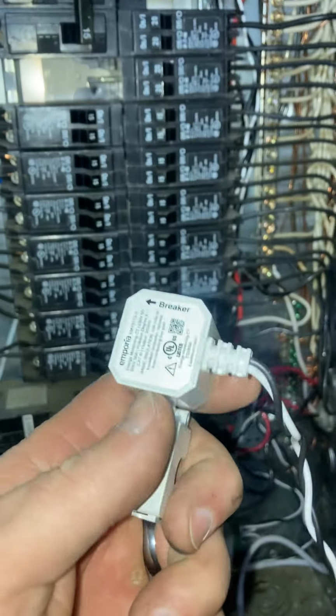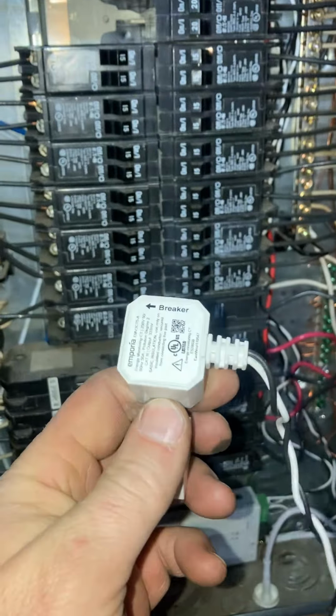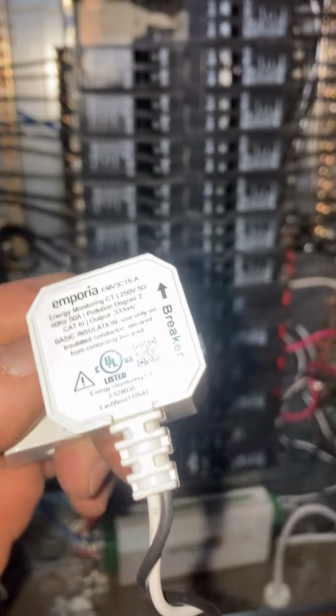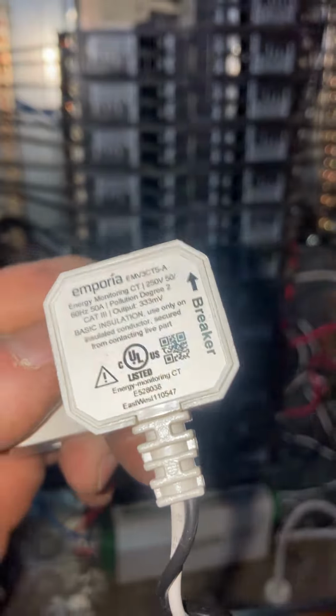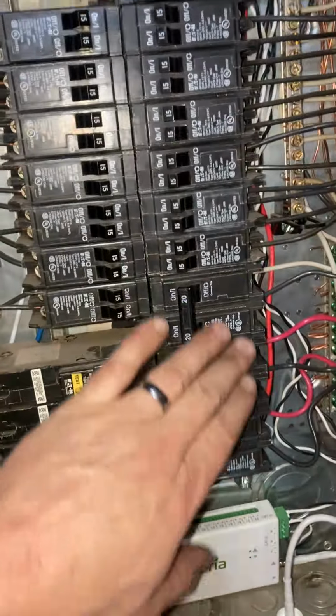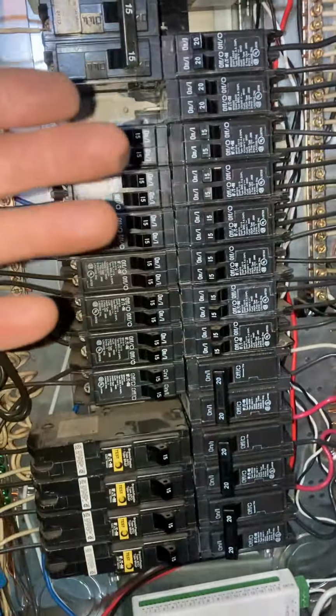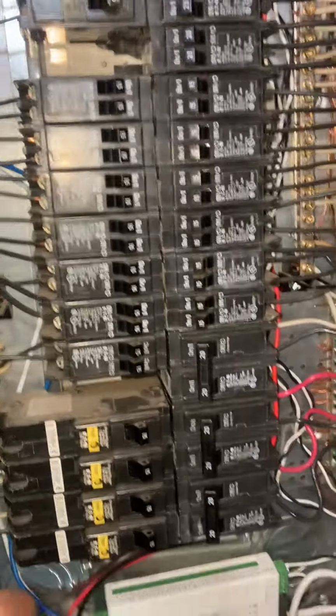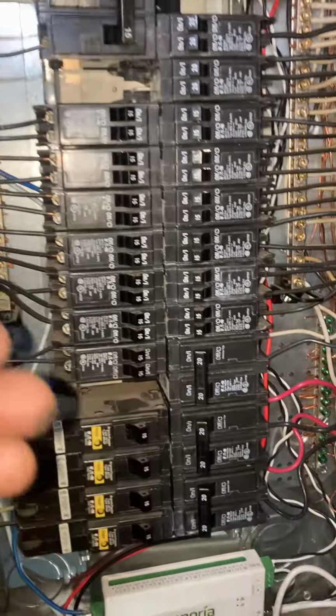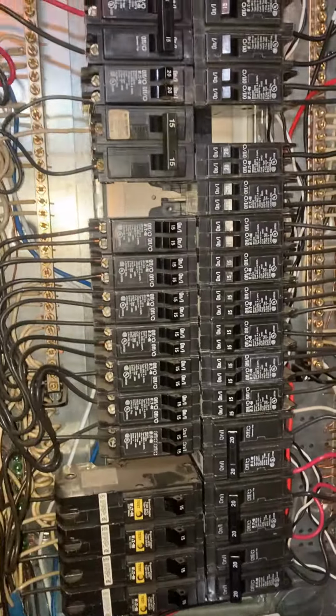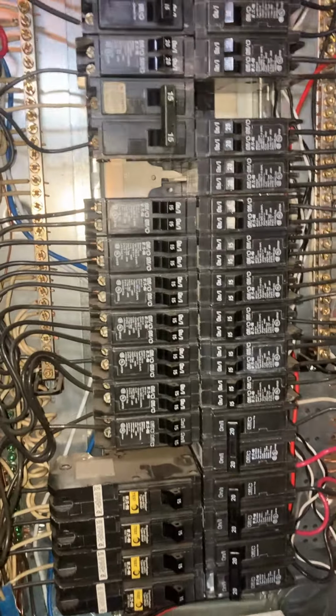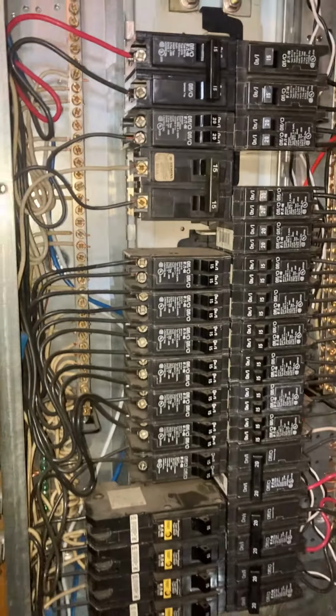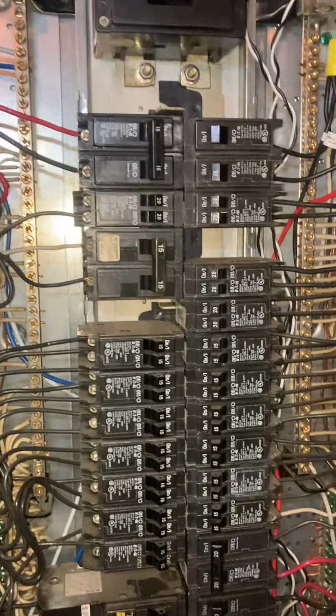In this case, I have 8 of these small current transformers, and they're good for up to 50 amps. So what I want to do is find the different loads in the house that are going to be the big ones: hot tub, water heater, heat pumps, electric baseboard, electric car, sub panel, maybe that's going up to the garage. I'm looking for all those big loads.